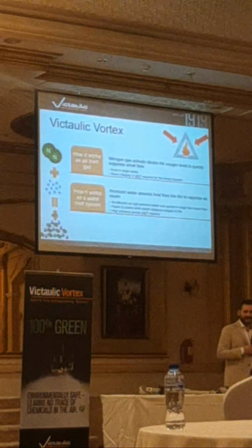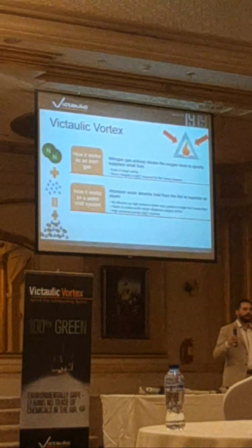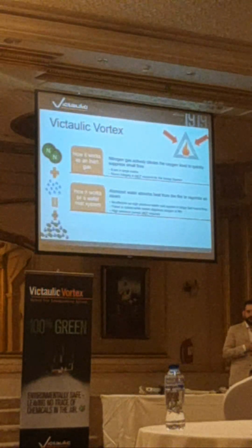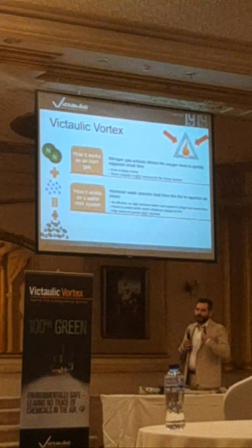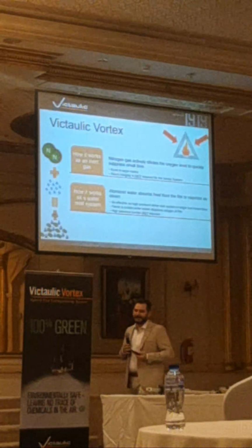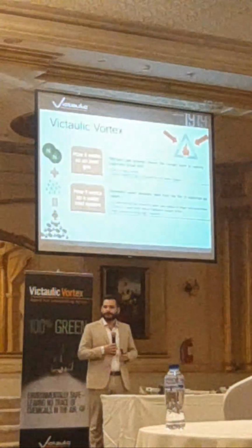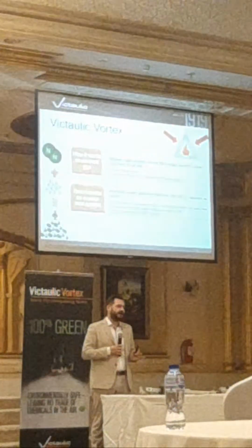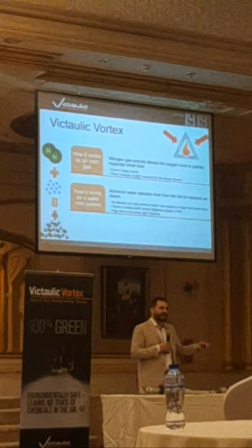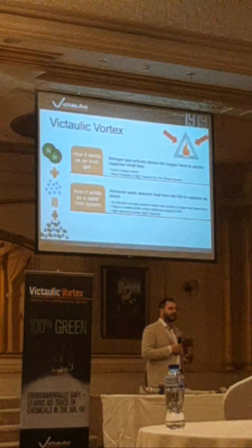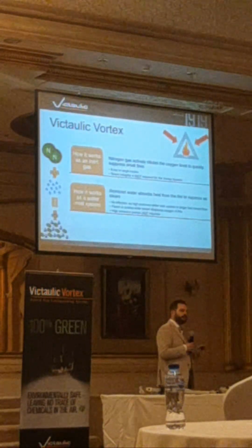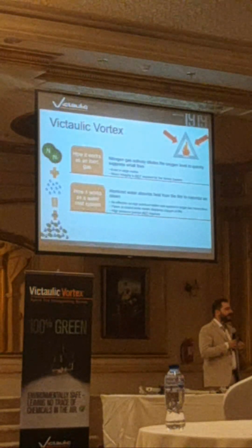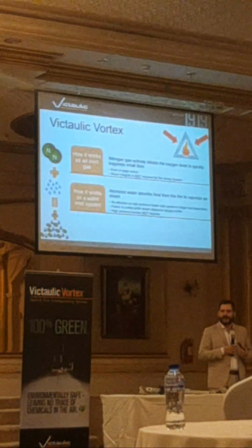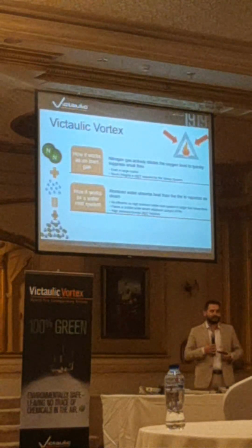So a little summary: what exactly do we do with the Vortex system? We're going to combine those two technologies together. So that's being hybrid. The biggest advantage against the gas is that we do not require full integrity. And the biggest advantage against water mist is that we're going to completely put out the fire. And in addition to that, the amount of pressure that we need on the water tank is going to be regulated from your nitrogen pressure. This means that you completely eliminate the pump, so you don't need to have maintenance on the pump, you don't need to pay for the energy that a pump costs, and you don't need to have a redundant pump as well.